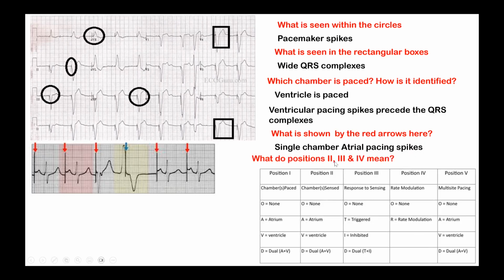What do positions 2, 3, and 4 mean in this? Usually, this is how pacing is described. Position 1, we say it is the chamber paced. Then position 2, the chamber sensed, then response to sensing and rate modulation. What is the meaning of what is being sensed? The intrinsic activity of the heart. Yes, it is not a pacemaker stimulation.